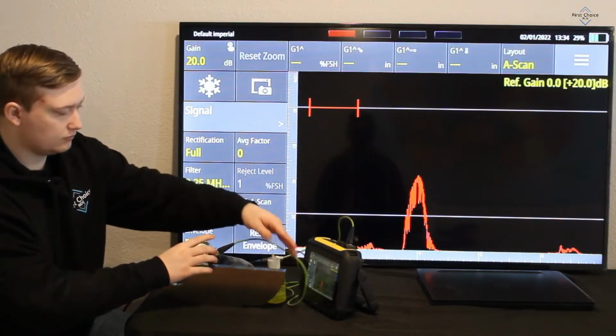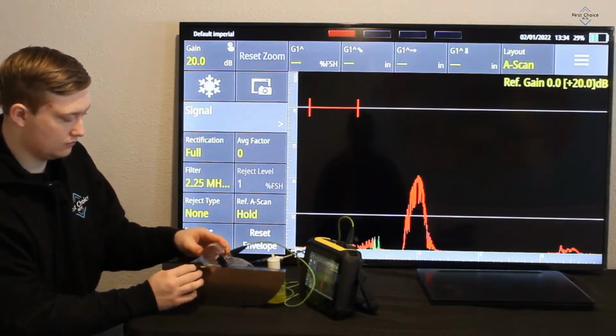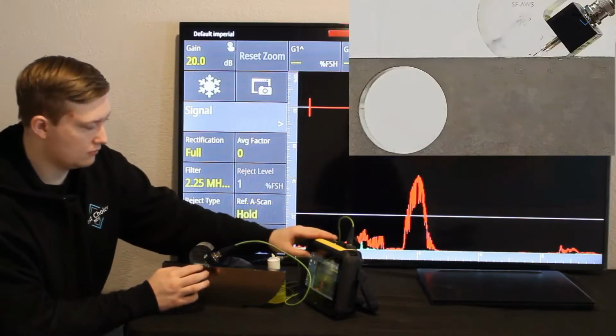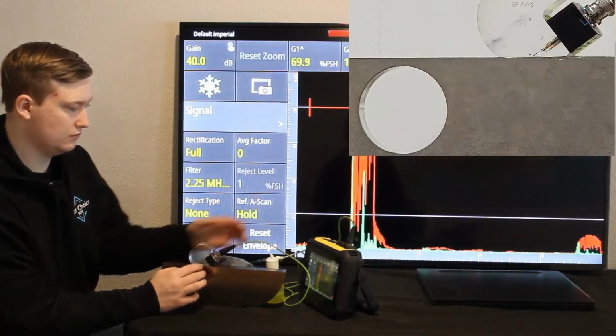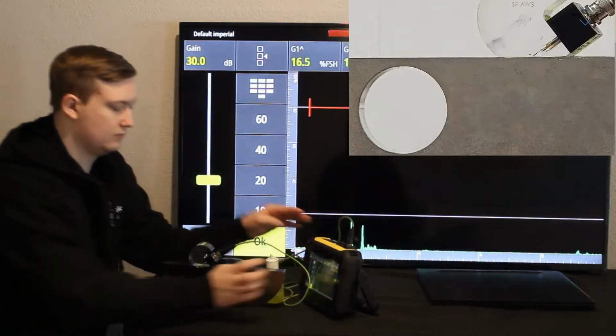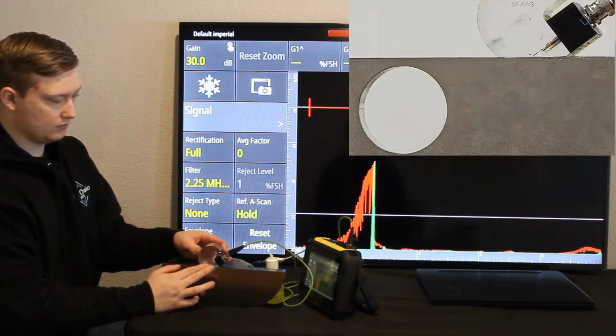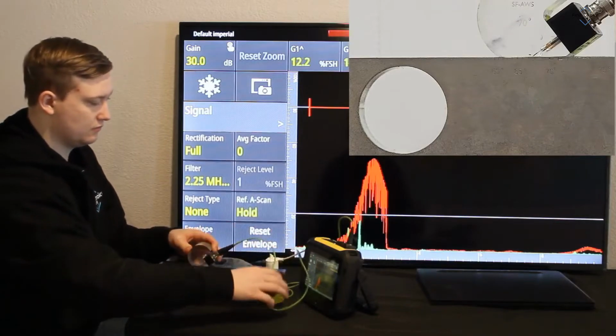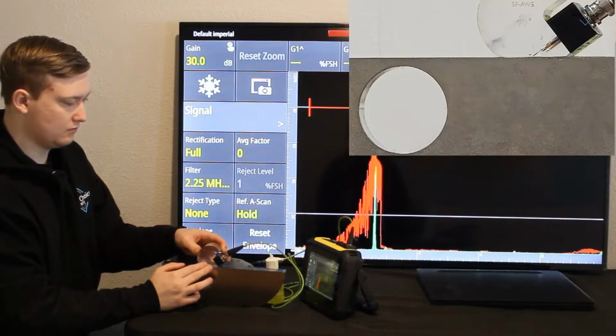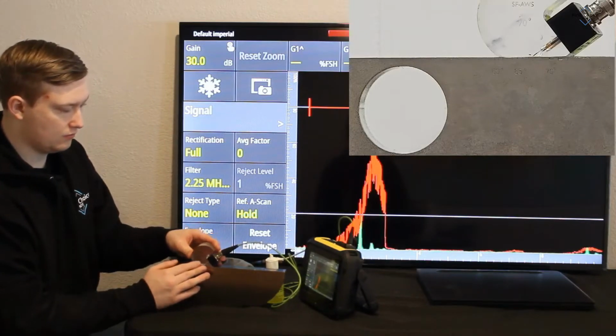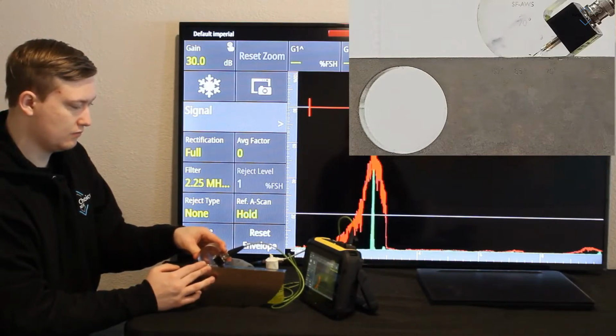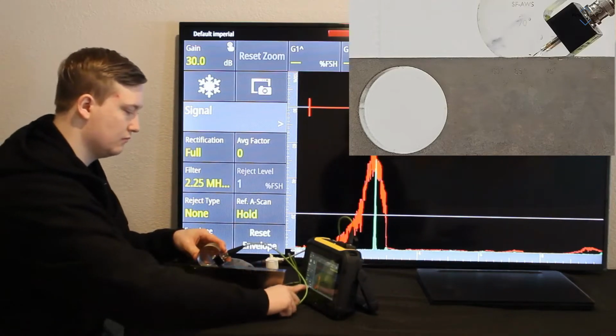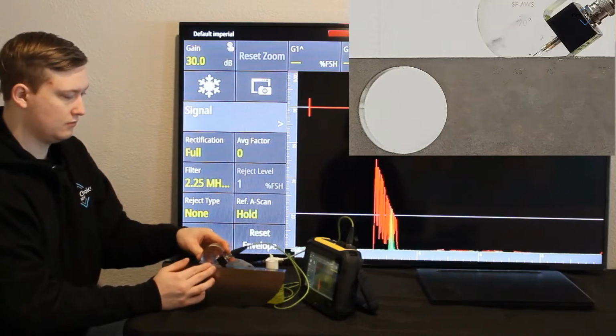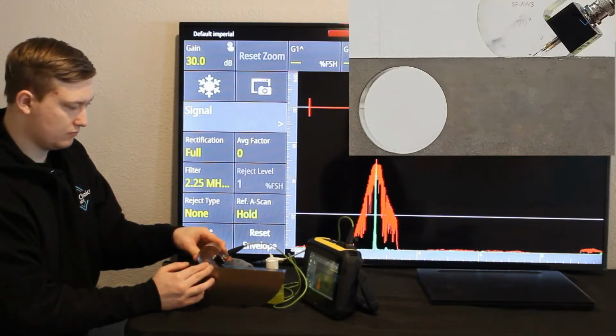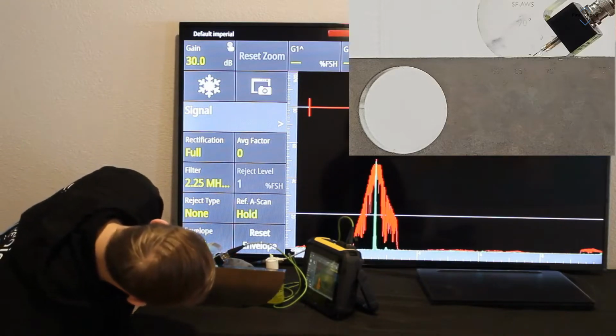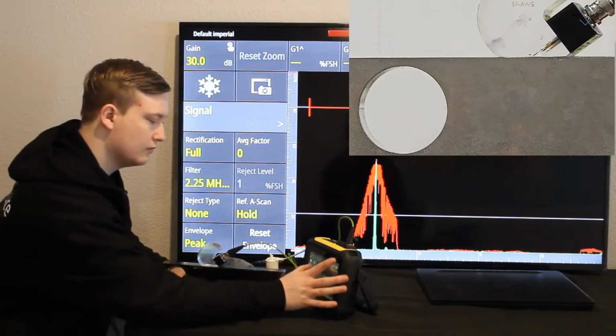So now I rotate the block and I'm going to be doing an angle verification. I'll be using that large radius hole there on the left side of the block. Since I'm using a 70-degree angle, it is a long, broad signal. So it is fairly hard to get the peak if you're not using an envelope, as I am. So here you clearly see a peak is being made. So I know it is right in the middle of that. So there we go, that's right in the peak.